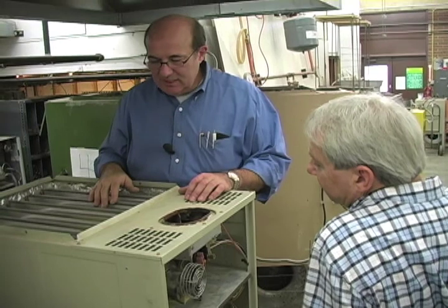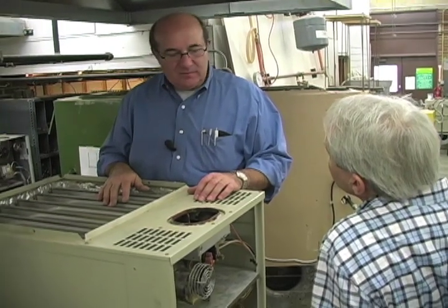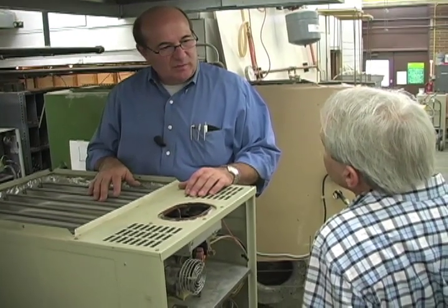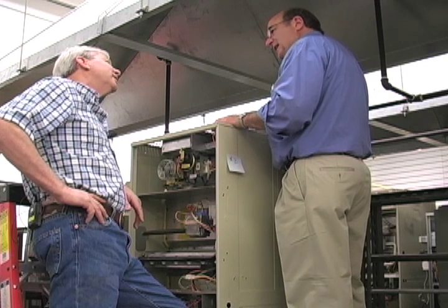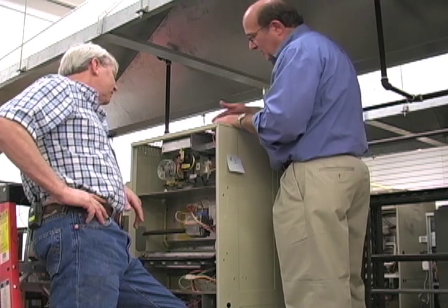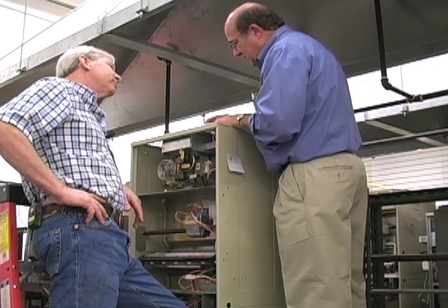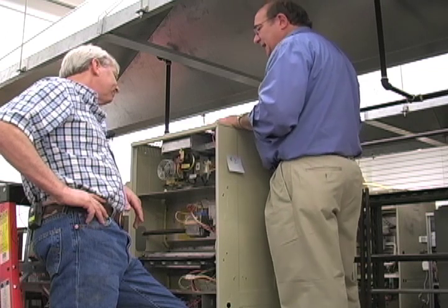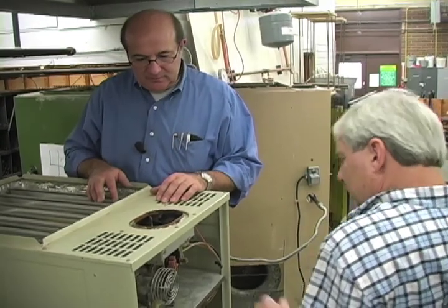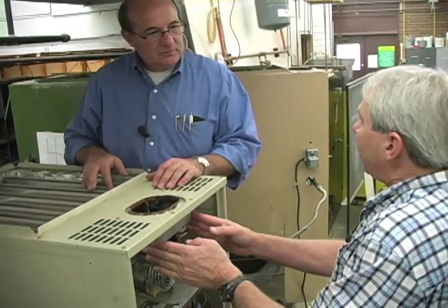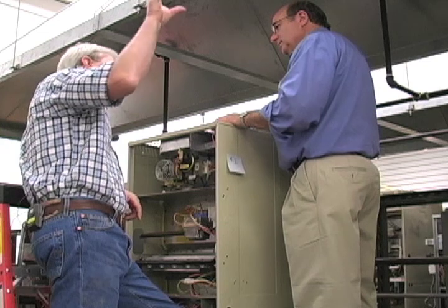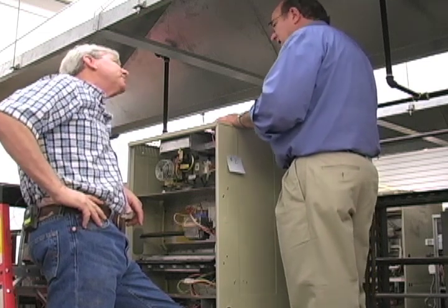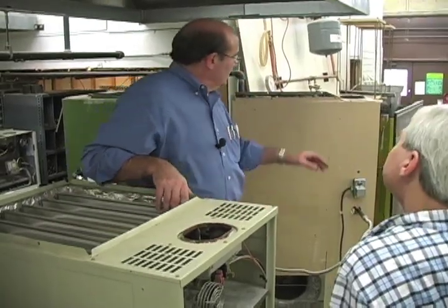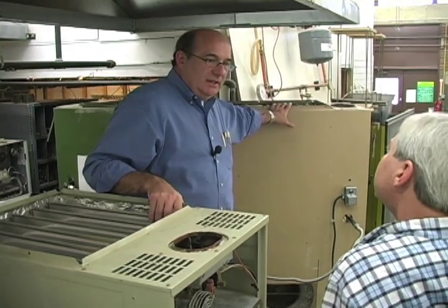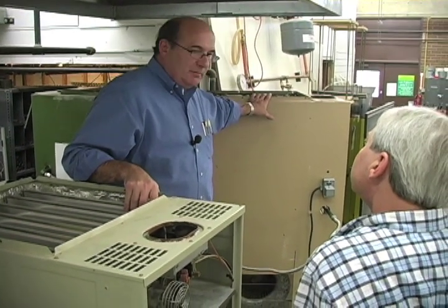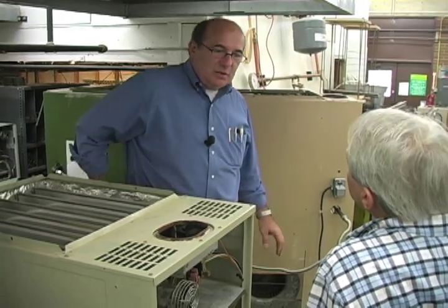So that's one big thing that we see when we have older furnaces replaced with these newer ones with much smaller flues, and you'll see that kind of corrosion. Now this one is an older furnace, but it's showing that corrosion probably just based upon age. Anyway, if an inspector is looking inside the furnace and he sees corrosion at the base of the venting system, it's a good idea to look at the exhaust vent itself and see if there's a problem of some sort.